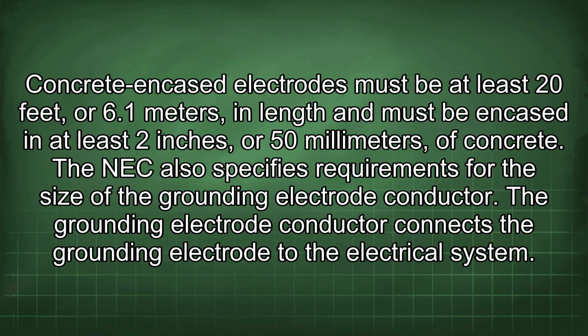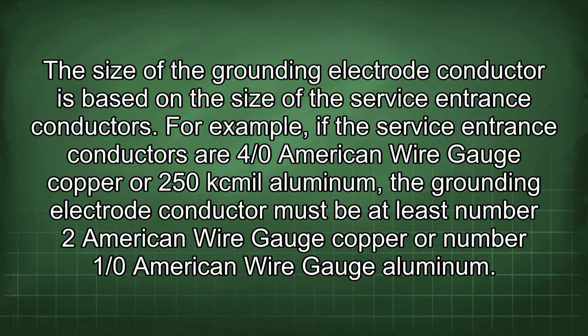The NEC also specifies requirements for the size of the grounding electrode conductor. The grounding electrode conductor connects the grounding electrode to the electrical system. The size of the grounding electrode conductor is based on the size of the service entrance conductors. For example, if the service entrance conductors are 4/0 American wire gauge copper or 250 kcmil aluminum, the grounding electrode conductor must be at least number 2 American wire gauge copper or number 1/0 American wire gauge aluminum.